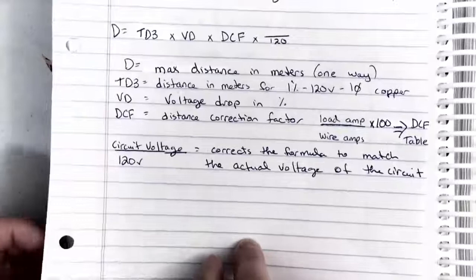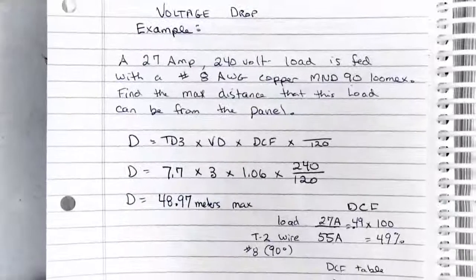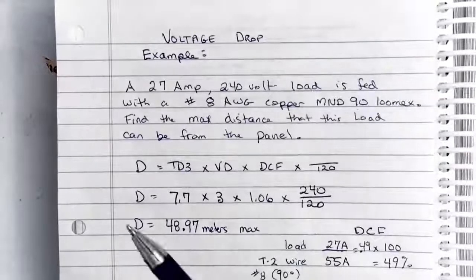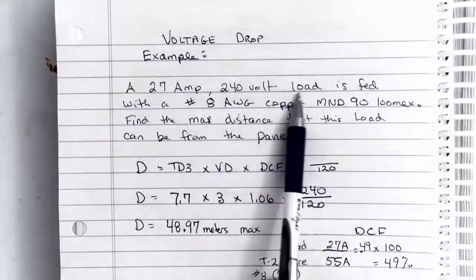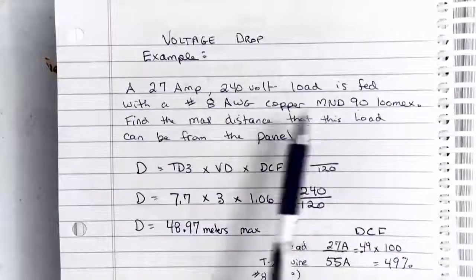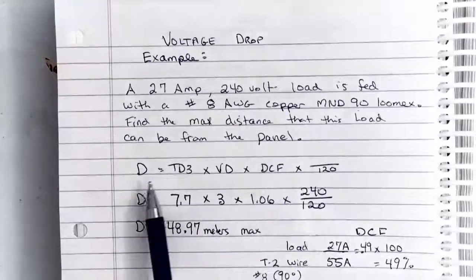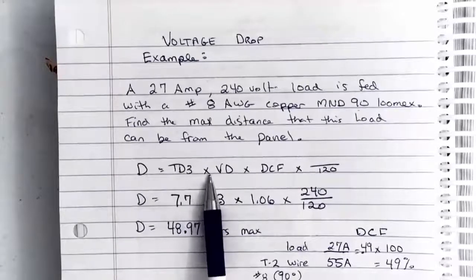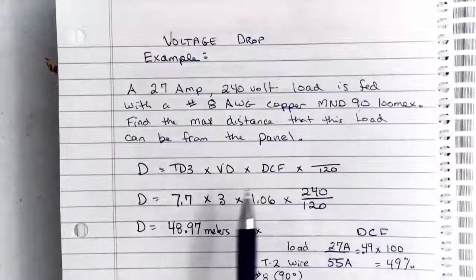So let's look at an example. Here's our example: a 27 amp, 240 volt load is fed with a number 8 AWG copper NMD-90 Loomex. And we want to find the maximum distance that this load can be located from the panel. We start with our formula: distance equals table D3 meters times the voltage drop times the distance correction factor times something over 120.